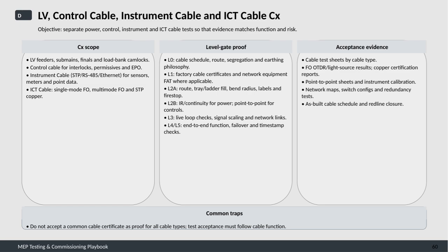Starting with the commissioning scope, it covers several key cable types: low voltage feeders, submains, finals, and load bank camlocks for power distribution; control cables that handle interlocks, permissives, and emergency power off signals; instrument cables, including shielded twisted pair RS-485 and Ethernet, which connects sensors, meters, and point data systems; and ICT cables, which comprise single-mode and multimode fiber optics, as well as shielded twisted pair copper cables. The level gate proof process is structured into multiple stages to ensure thorough verification.